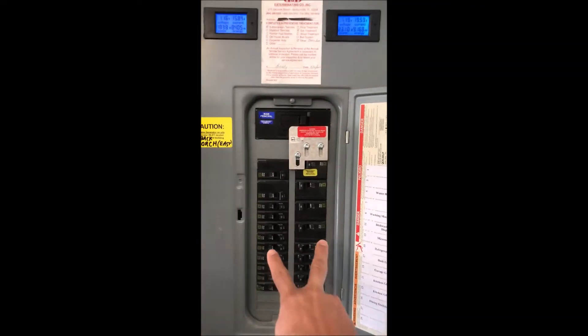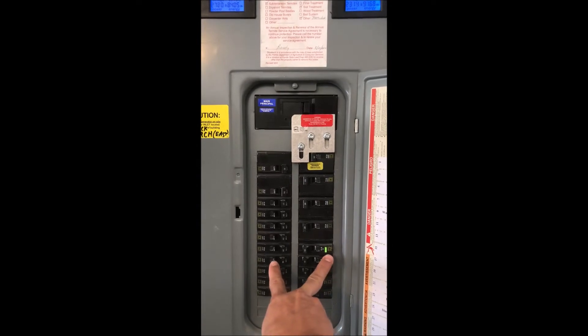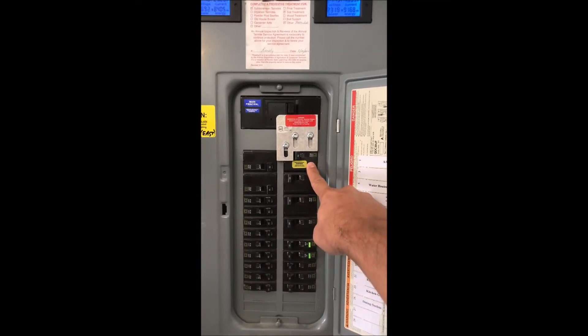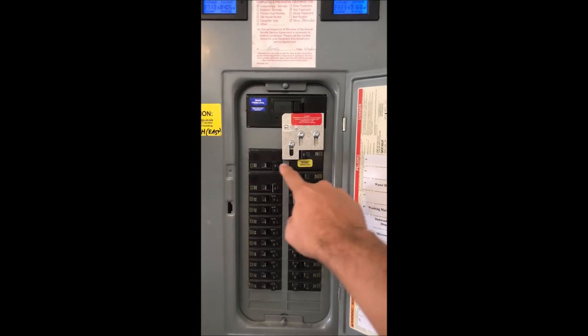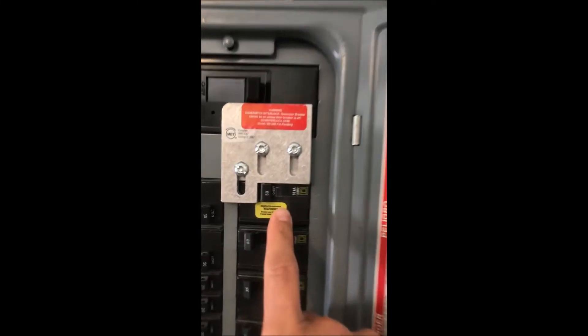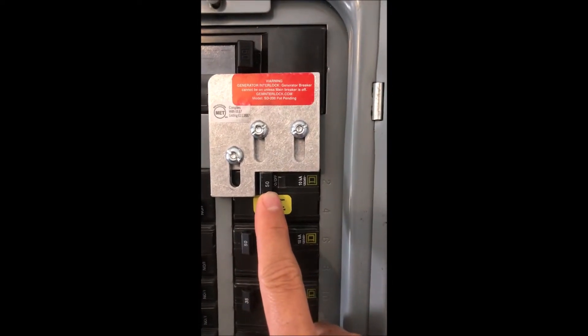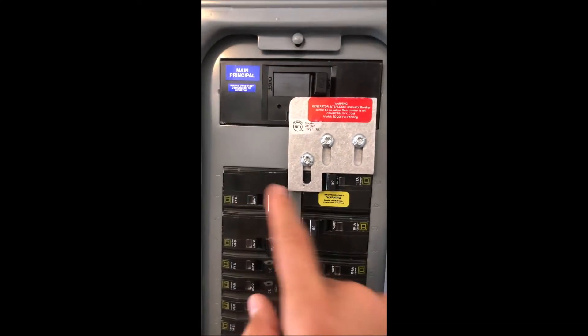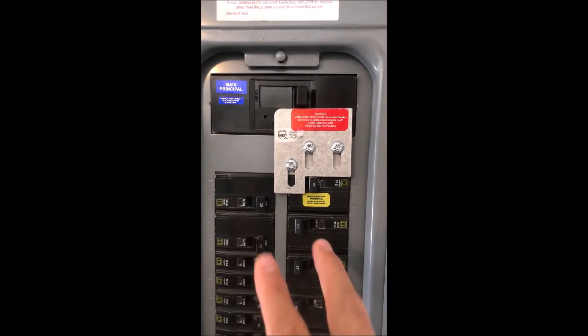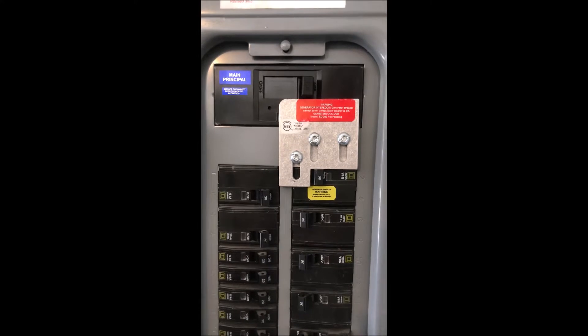You can see right here, you've got two buses — two buses are each 120 volts each. You have to use what's called a double-pole breaker so that you can supply power to both buses. You've got bus 1 and bus 2. If this is a 50 amp double-pole breaker, double-pole means that it serves two buses in your breaker panel. 120 volts on each bus gives you 240 volts of power capability.